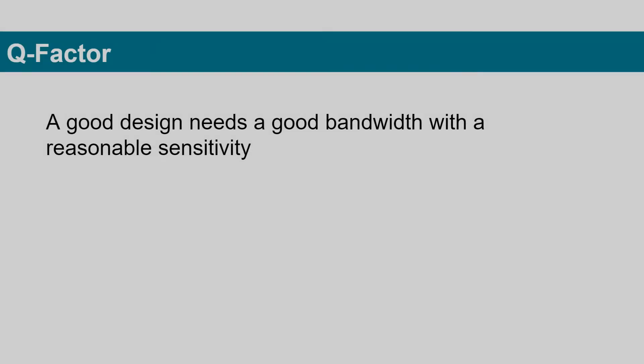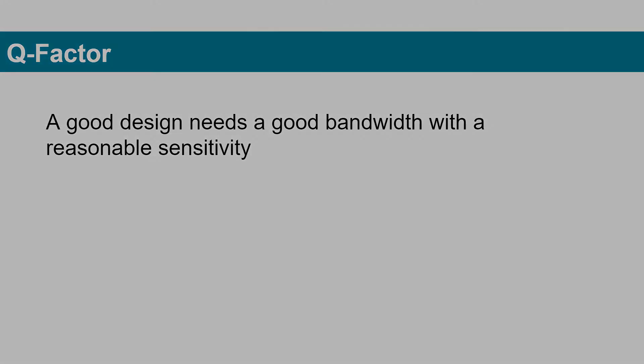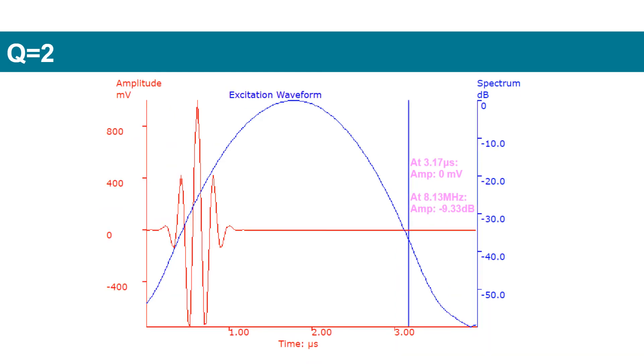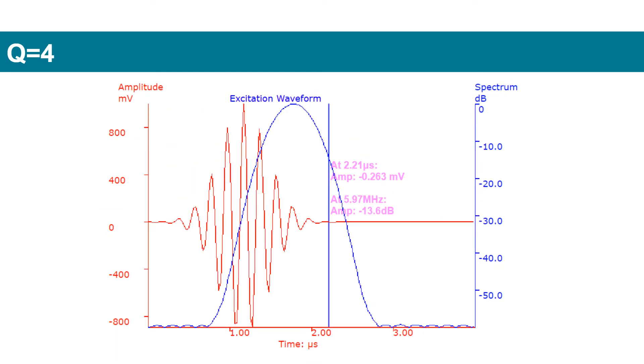A material with a high acoustic impedance will do the job. However, too much damping will also decrease the sensitivity dramatically. Therefore, a good design needs a good bandwidth with a reasonable sensitivity. You can easily see the differences of excitation waveforms with different Q-Factor.